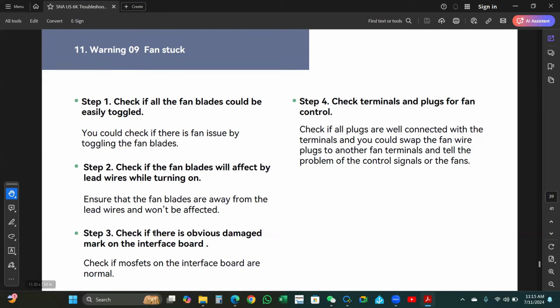Step 3. Check if there is an obvious damage mark on the interface board. Check if the MOSFETs on the interface board are normal. Step 4. Check the terminal and plug for the fan control. Check if the plugs are well connected with the terminals, and you could swap the fan wire plugs to other fan terminals to tell whether the problem is the control signal or the fan or fans.